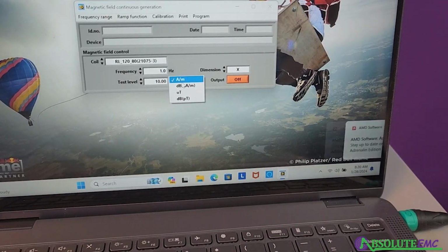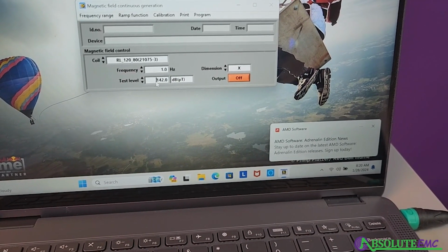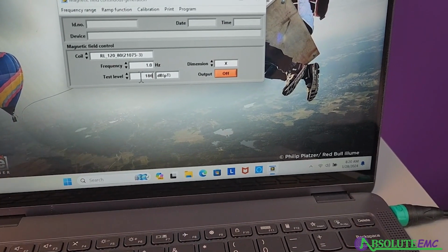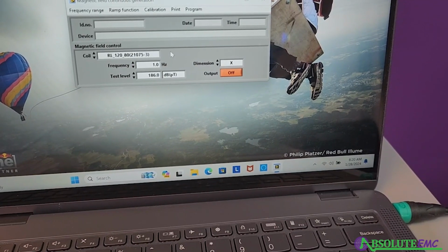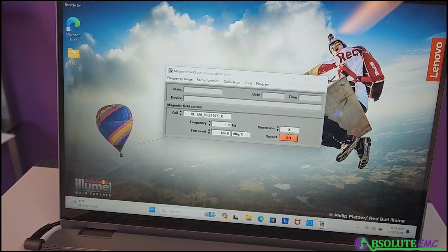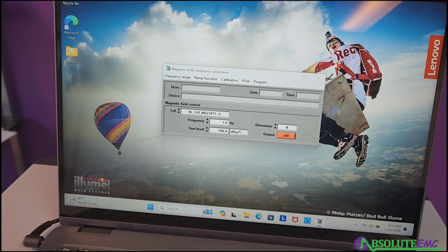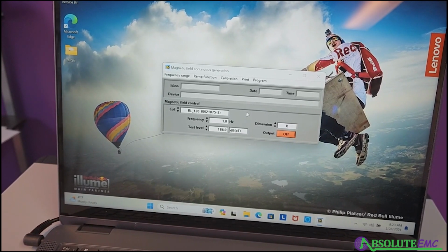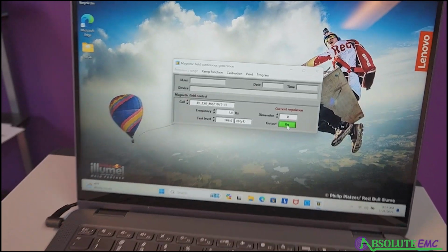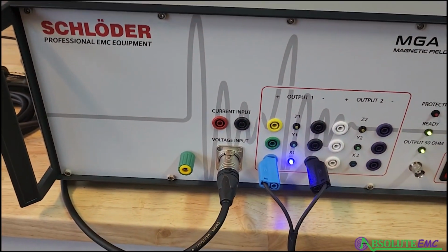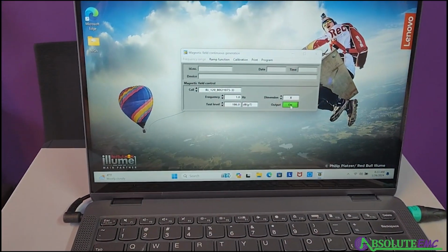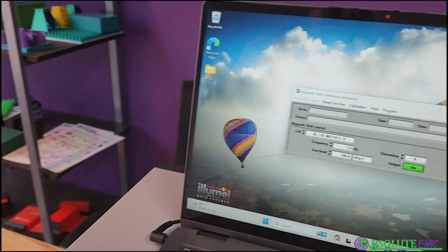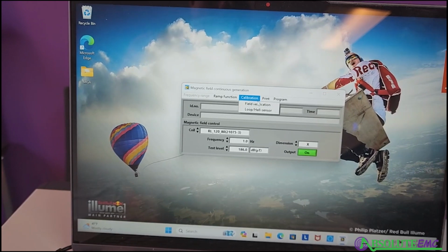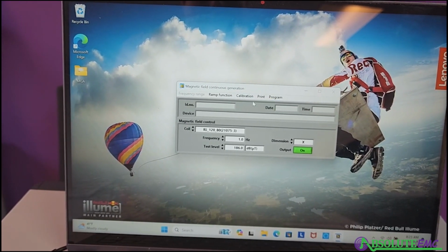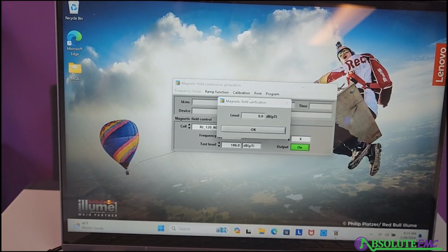And we can change the test level we're going to do. Say, dB. Let's go 186. We got 1 hertz set up, 186 dB picoteslas. We're on dimension X, so we could hit and turn on the field. Turn on the field. This light indicator comes on. But are we doing the right field? We do. It's calibration, field verification. There we go. So right now it's measuring the field verification from the Hall sensor.